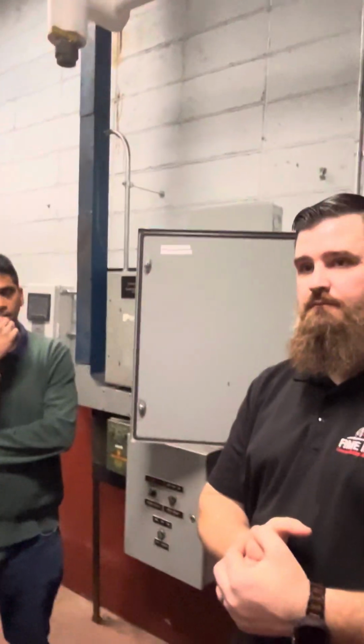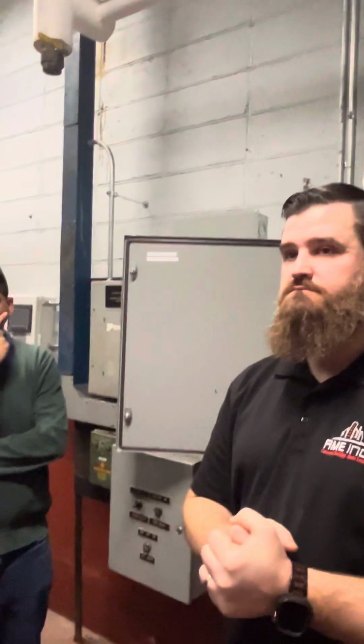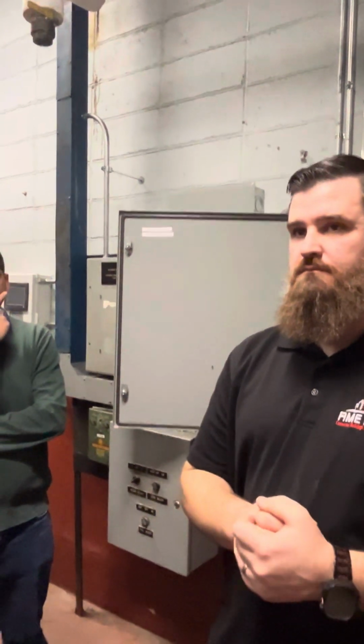Wait, that's a mistake - that's not going to happen, because this boiler should never run when those 3 boilers are on. That's entirely separate, I don't care about that. All I know is if I have 4 boilers running for any reason, we're going to fire that at 100%. So the way it just works, from what I understand, and that's wrong on your end - it's supposed to be 1/3, 2/3, 100% in those 3 boilers. That's the way it's supposed to run.